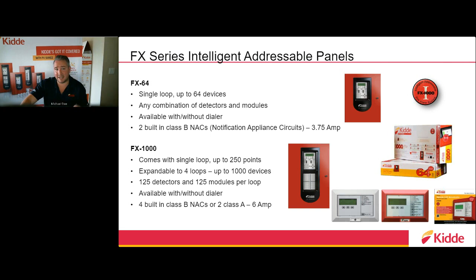For example, on an FX64, it's a single loop panel. Now on the FX1000 packaging, it will show you that it has that scalability. Keep this in mind. For NAC circuits, keep in mind you have about 1.5 amps per NAC to be safe. Also, we can fit up to 8 remote annunciators off each platform for our intelligent panels.